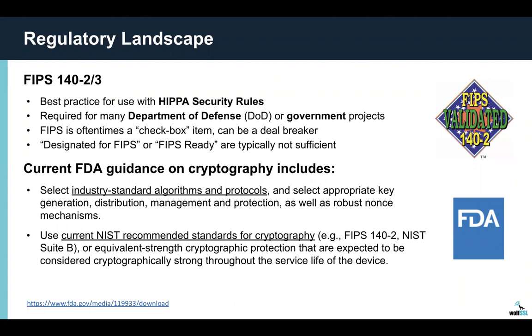The current FDA guidance does include some wording on cryptography. It recommends that you use industry standard algorithms and protocols. It also suggests that you use current NIST recommended standards for cryptography, and this is where FIPS would come into play with FIPS 140-2 and NIST Suite B.